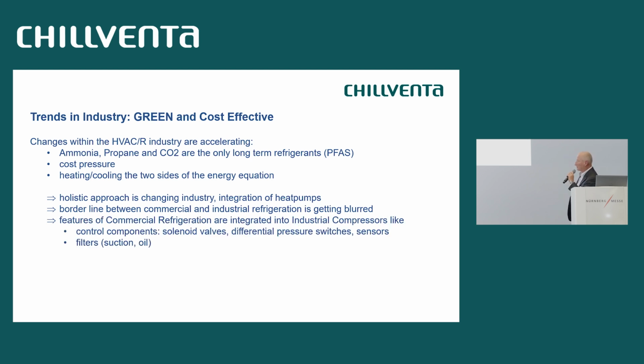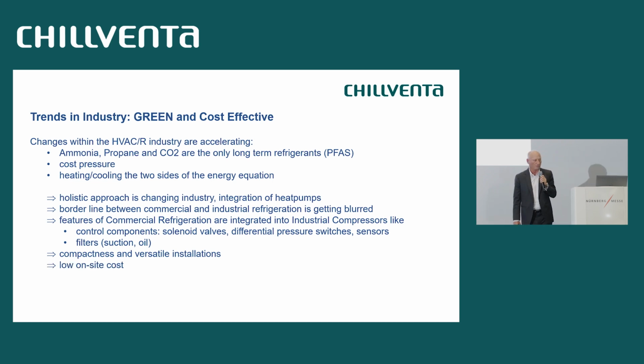The features of commercial refrigeration are integrated into industrial compressors. When in previous times an industrial compressor was just a bare shaft block, now more and more it is integrated, control components, solenoid valves, differential pressure switches, sensors, filters, and it is changing also the design of our industrial compressors. Compactness and versatile installations are key. Space is premium, it costs money. On-site cost is something we all try to avoid.